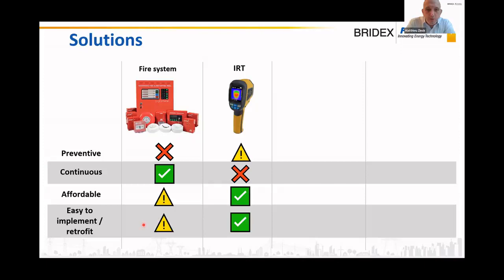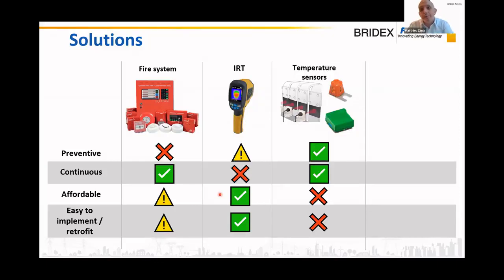Then one of the mandatory actions in most of the countries is to have infrared thermography. The infrared thermography is of course somehow preventive if you do it regularly, but it's definitely not continuous. It can be regarded as affordable and easy to implement, although you need to open the panels and sometimes it's not always very secure. Then another solution is, of course, to use sensors. There are various types of sensors available on the market, whether it's corded or wireless. Of course, they are preventive because they allow you to monitor the temperature and sometimes very accurately. It's continuous, and it's not always very affordable and not always very easy to implement or retrofit, especially when it comes to corded sensors.